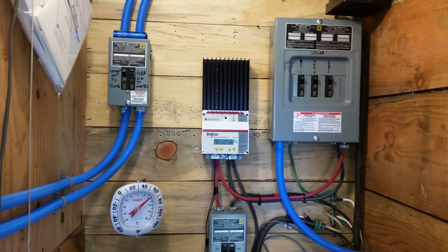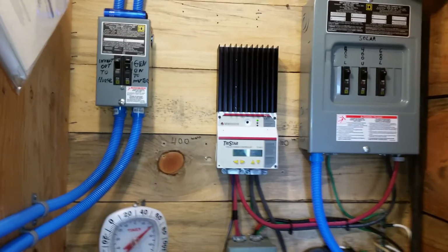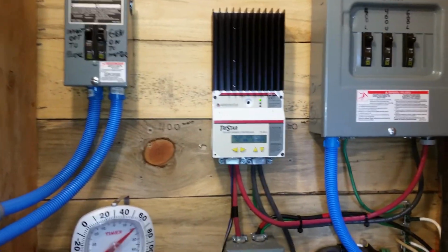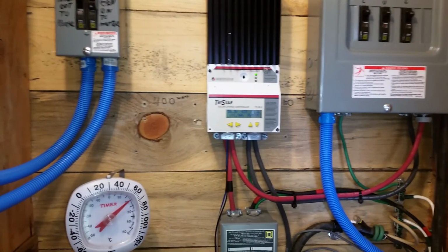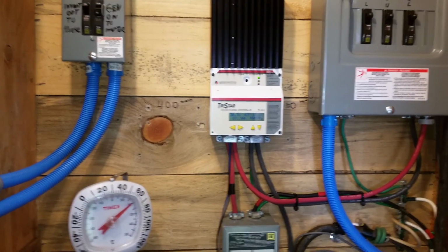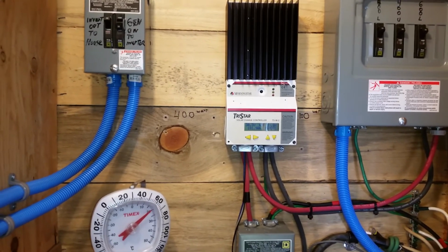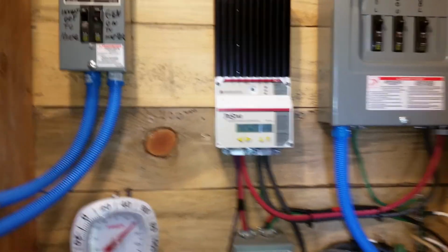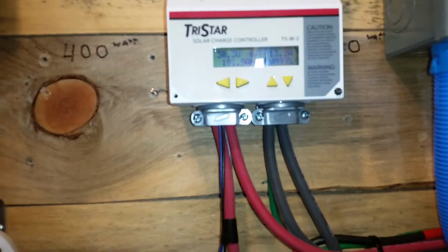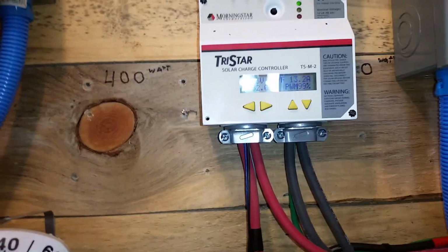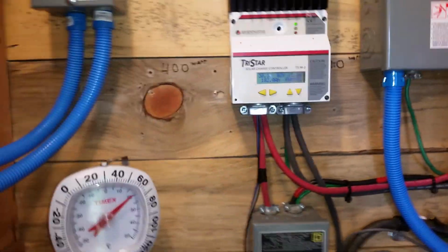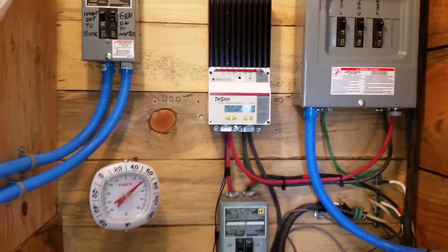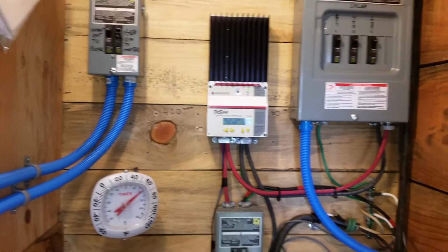You'll notice with PWM charge controllers that the voltage coming in from the solar array is very close to the voltage of the battery system. You'll note that I'm at 30.3 volts now. It's doing its absorb cycle. But this is a 24 volt system, 24 volts nominal.